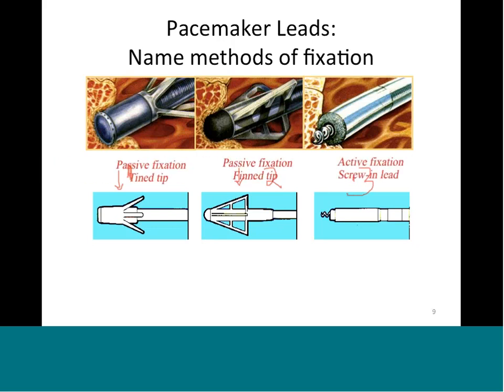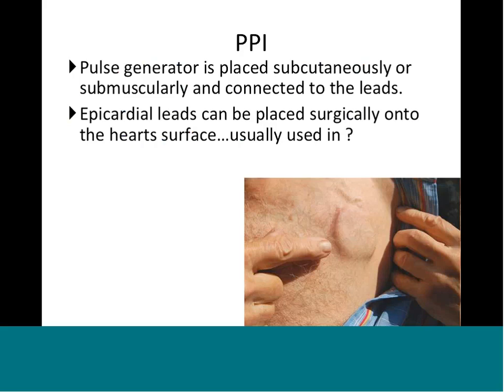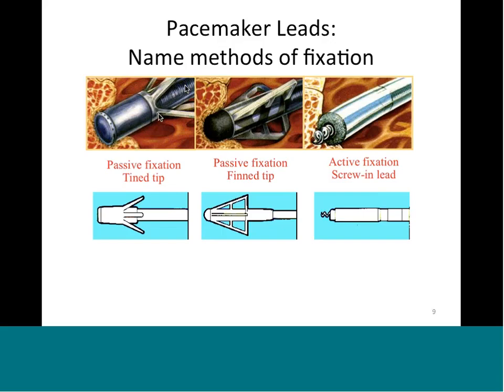The other two are what are called passive fixation. In passive fixation, you don't screw anything in - you just put it there and it touches the tissue. The first two are passive fixation, with a fin-like tip, and the third one is your screw-in lead. So those are the methods of fixation of pacemaker leads.